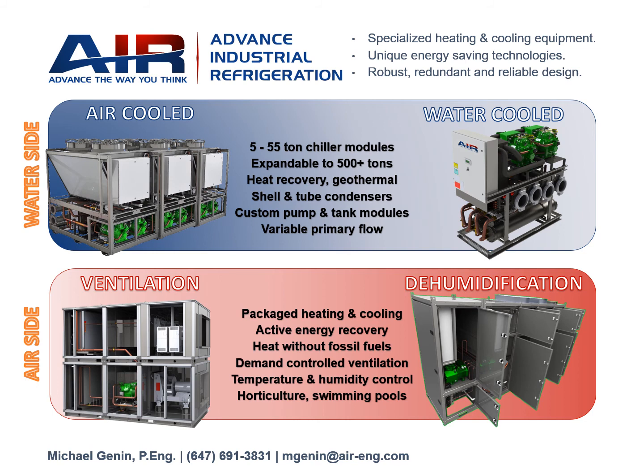I have some questions I'm going to answer that come in typically. The first is, can it be used for toilet exhaust? And the answer is absolutely. With this unit, you can pass many types of different exhaust through it. That's really one of the main advantages, with no risk of cross-contamination. In some very extreme examples, we had exhaust air that was contaminated with ethanol vapor. Certainly nothing you would want to run through a traditional heat wheel. And we are able to build the exhaust section of the unit spark proof to handle that. Again, another great example of untapped energy sources.